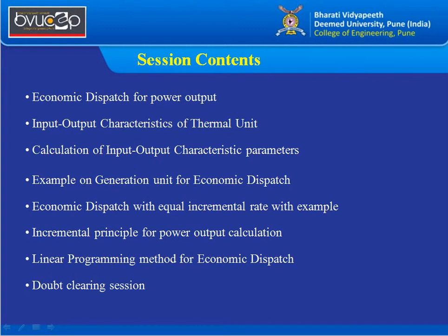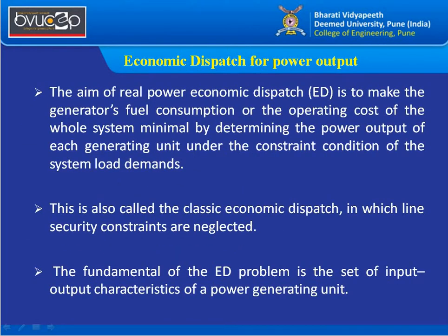The aim of economic dispatch is to achieve economy in real power generation. Real power generation must be minimized in terms of fuel consumption and operating cost. This is obtained by calculating the power output from generating units that satisfies load demand under certain constraint conditions. When security constraints are neglected, this is the classical economic dispatch method; when security constraints are included, it becomes security-constrained economic dispatch.